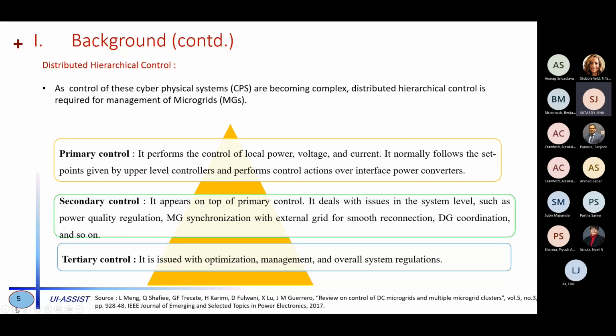Primary control handles the sharing of local power, voltage regulation, and local load current sharing, and it's the normal primary control used for converters. Secondary control is built on top of primary control, sending compensation terms to the primary controller to achieve more accurate power sharing and tighter voltage regulation.